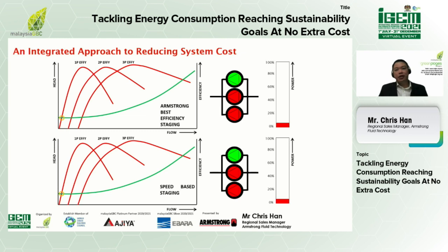This slide shows two different methods. Above, we call it the best efficiency staging, where the pumps are staged on and off based on best efficiency. And below is the traditional approach of staging the pumps based on pump speed. The bottom graph is very typical of how the BMS controls, where the pumps are staged on around 95% of full speed and off at 55%. And this traditional staging, based on full loading of the pump, will not optimize the system.